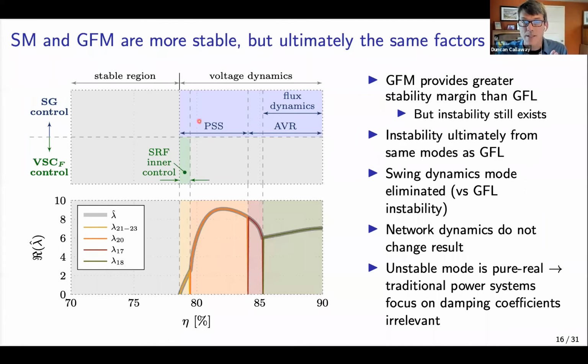Something important to note is that the swing dynamics, and because there's no phase lock loop on the grid-forming converter, also the PLL dynamics, no longer emerge as an important source of the instability. Once again, I'll show you in a second that network dynamics don't change this result.